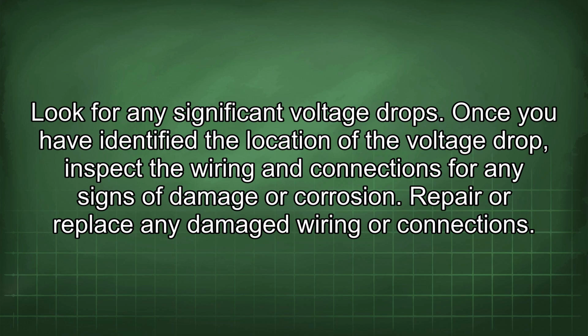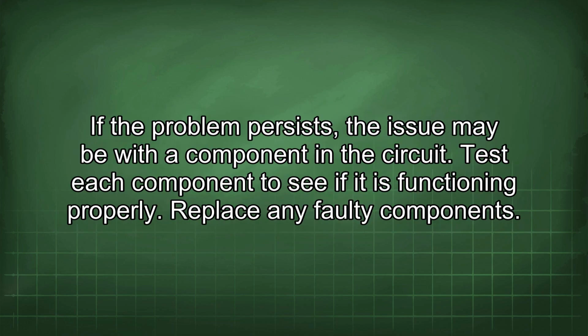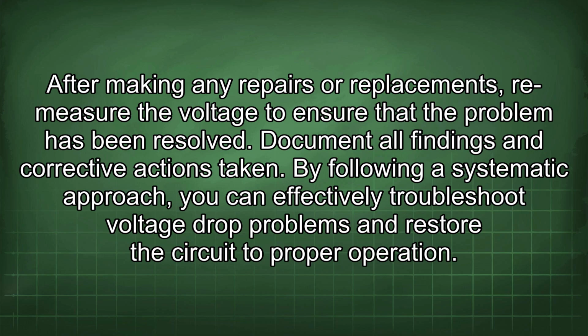Once you have identified the location of the voltage drop, inspect the wiring and connections for any signs of damage or corrosion. Repair or replace any damaged wiring or connections. If the problem persists, the issue may be with a component in the circuit. Test each component to see if it is functioning properly. Replace any faulty components. After making any repairs or replacements, remeasure the voltage to ensure that the problem has been resolved. Document all findings and corrective actions taken. By following a systematic approach, you can effectively troubleshoot voltage drop problems and restore the circuit to proper operation.